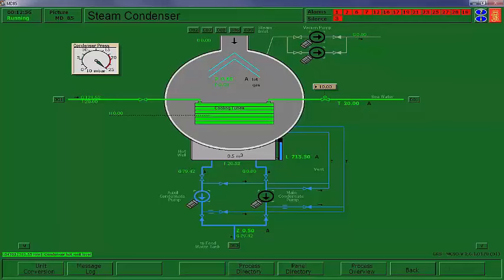One thing to realize on this too, this unit uses vacuum pumps rather than an air ejector. So we're not really worried about using the condensate in the hot well as a coolant. So we could pump that even dry if we wish to, but there's no reason to. And by the way, you notice that a small amount is led back as a recirc. Okay. So next thing we're going to do is supply heating steam to all the different services.